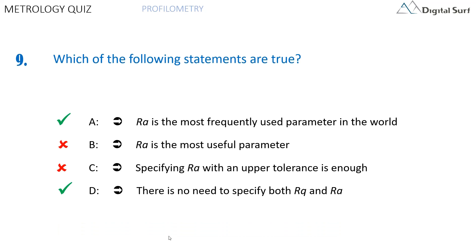The correct answers are A and D. All studies show that RA is the most frequent parameter mentioned on drawings — it is also the first parameter used in history, once called CLA (Center Line Average). But it does not mean it is the most useful or the most efficient. In most cases, it barely correlates with the surface function unless very specific filtration conditions are applied. When specifying RA or another roughness parameter, it is important to document the filtration condition, cutoff, and filter type if not Gaussian — otherwise the tolerance is meaningless. The two parameters RA and RQ are totally correlated to each other; you can use one or the other, but there is no need to use both. RQ has the advantage of having a physical meaning and should be preferred over RA.